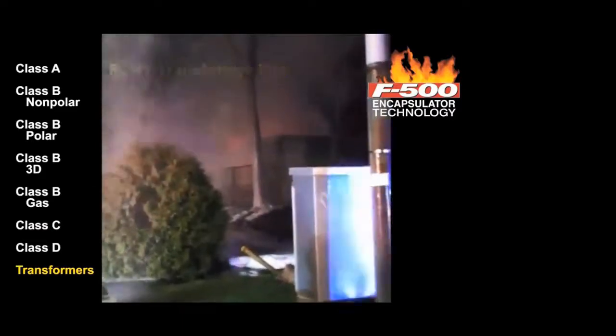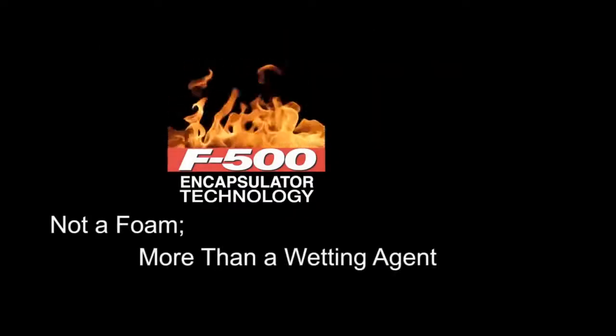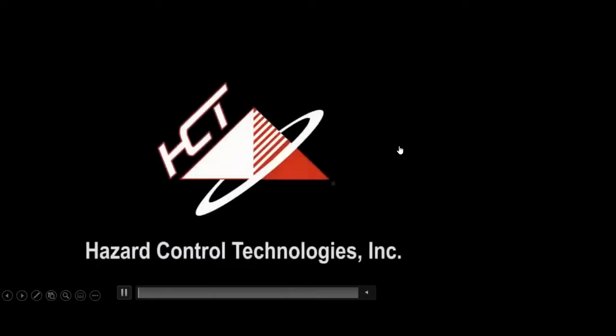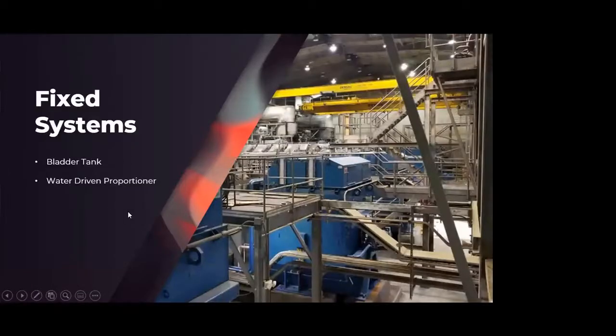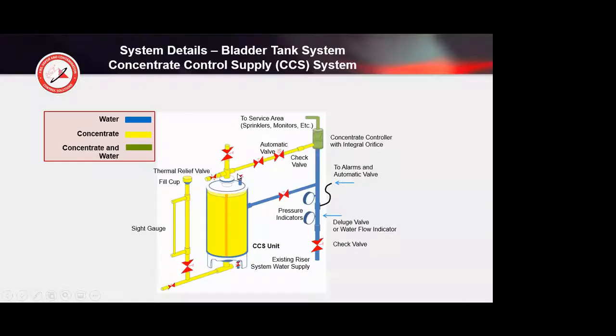There you see they start to apply the encapsulator agent. It's knocked down. Fixed systems. When we talk about putting it into sprinkler systems, we have two different types of concentrate control supply systems. One is a bladder tank system and one is a water-driven proportioner system. So this is your typical layout of a bladder tank system. This just shows a one riser configuration. You can have a multiple riser configuration. Could be 2, 3, 4, 5 risers.